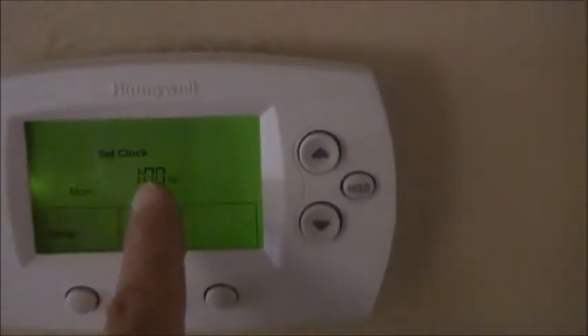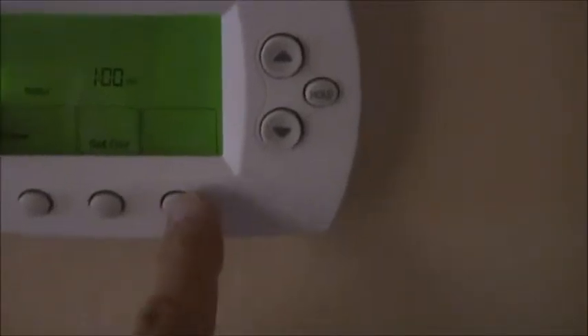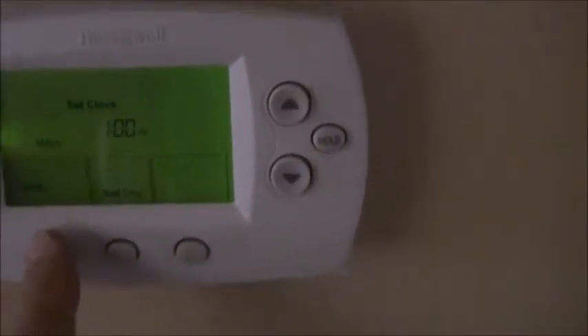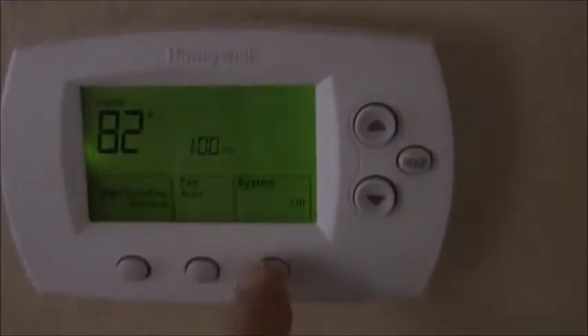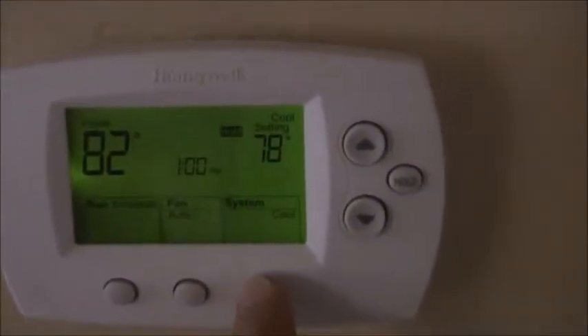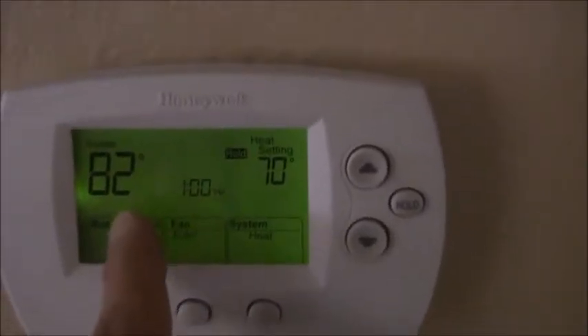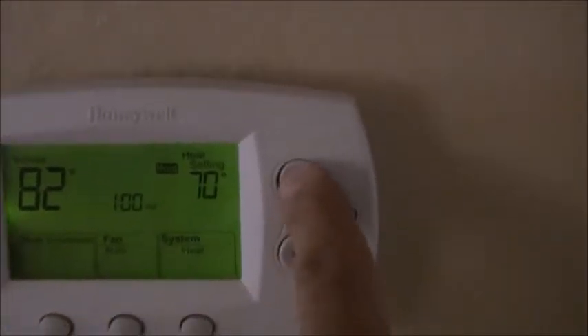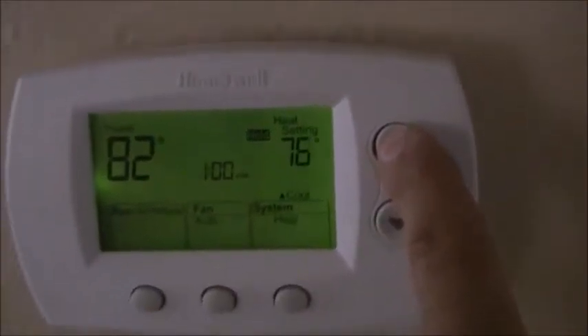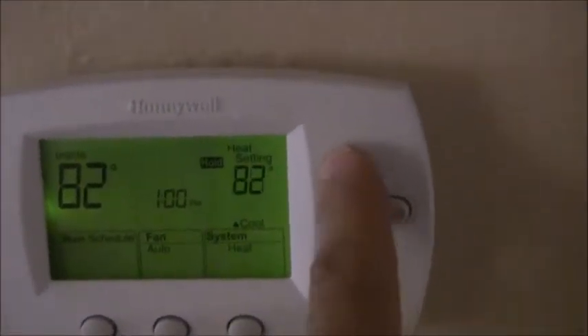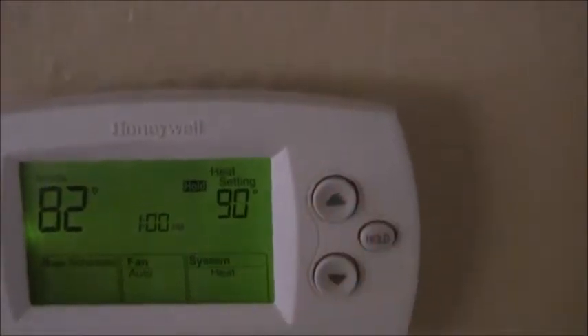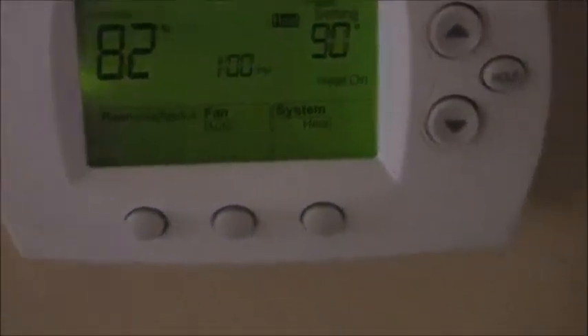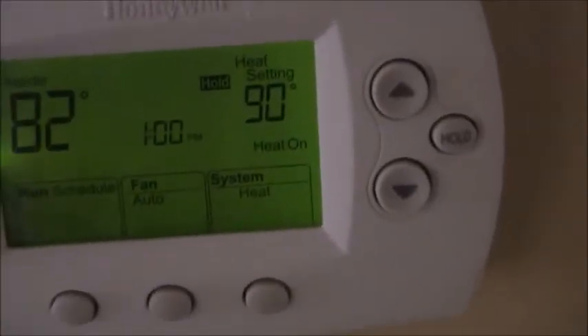Alright, here's the thermostat. Set clock. It lost its memory because I unplugged it upstairs. Let's not worry about that. Oh, it's going to make me do that right now. Wait a second, see if I can bypass that. Alright, I'm going to go to System, I'm going to go to Heating. It's currently set at 82, so I have to go higher than 82. Let's see how high the system will let me go. Come on. 90, it'll let me go up to 90. Alright, so right now the heat is on and the unit should absolutely light off. So let's go see it light off.